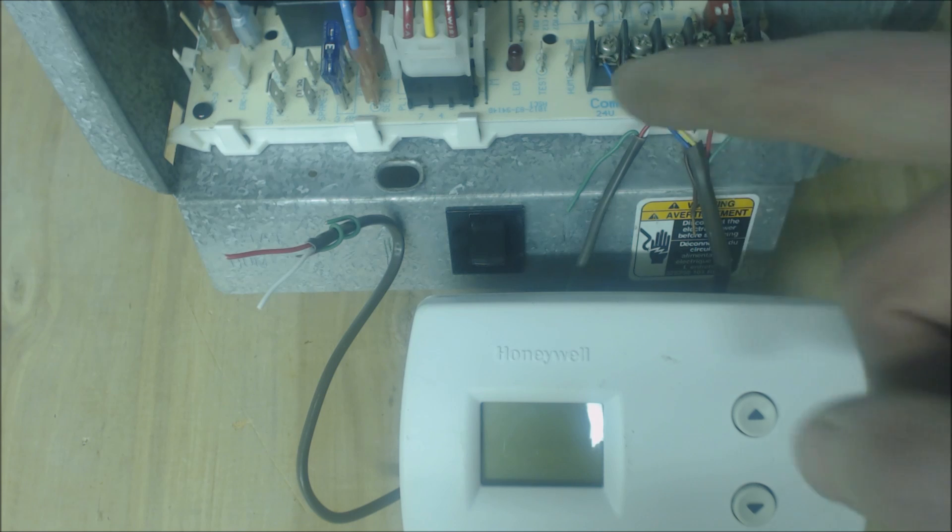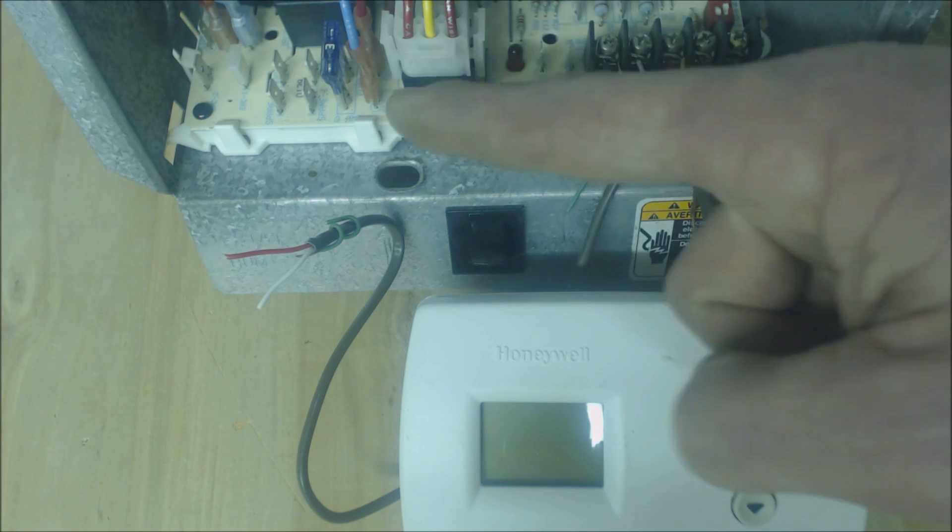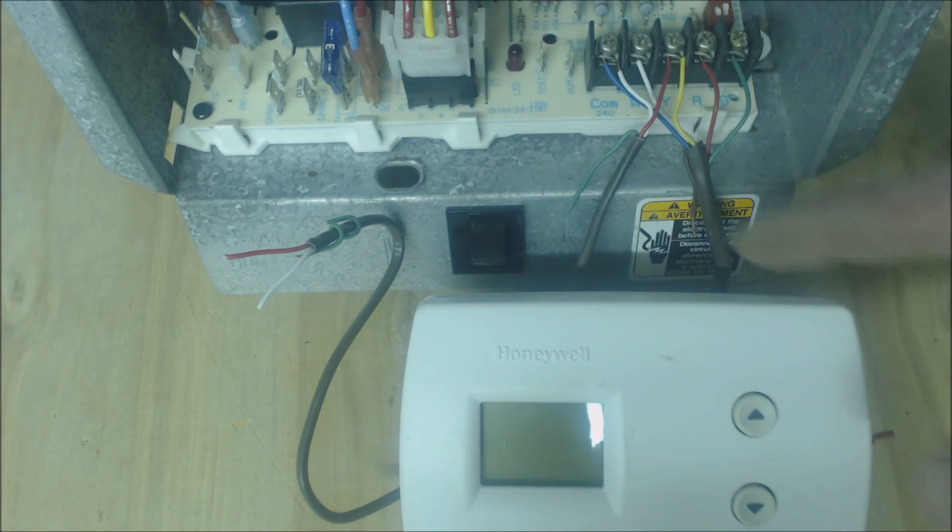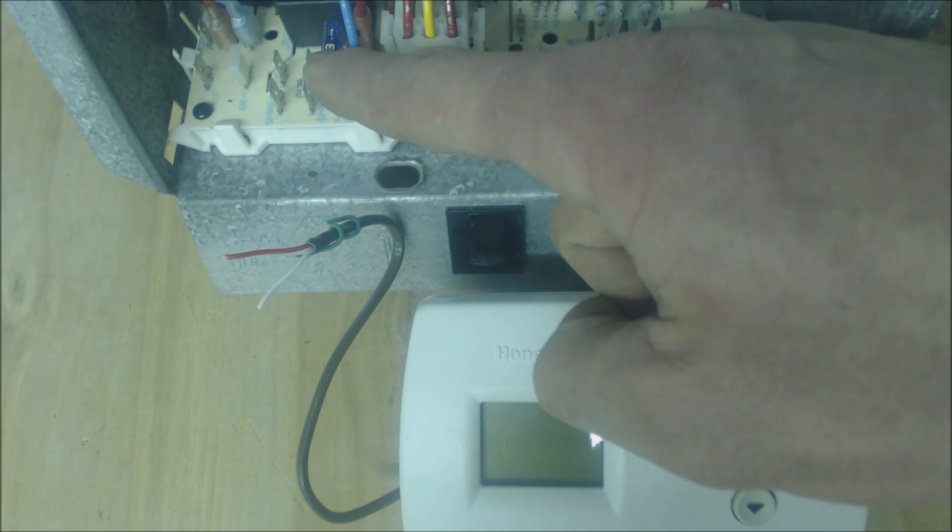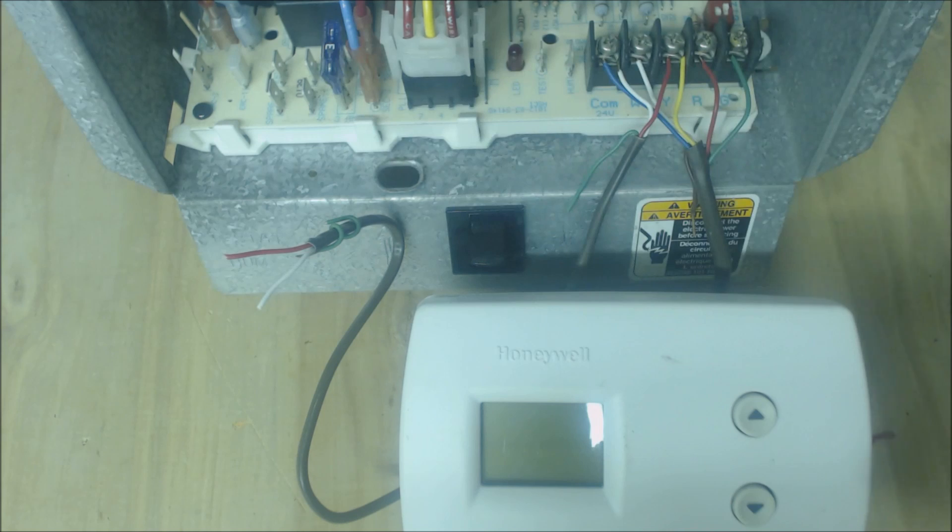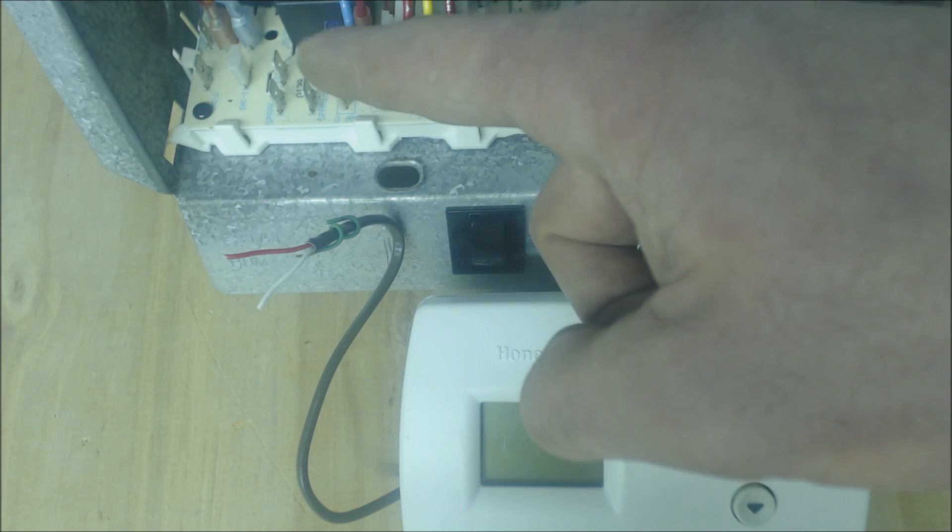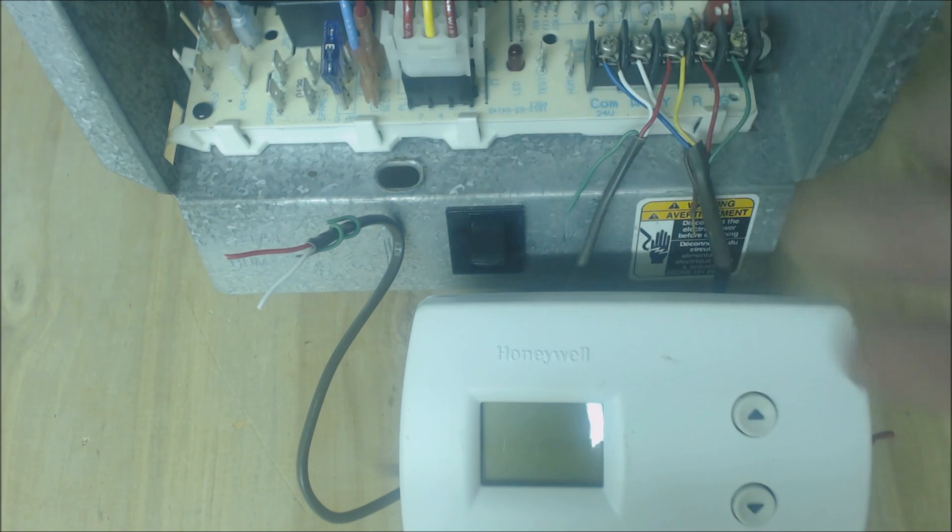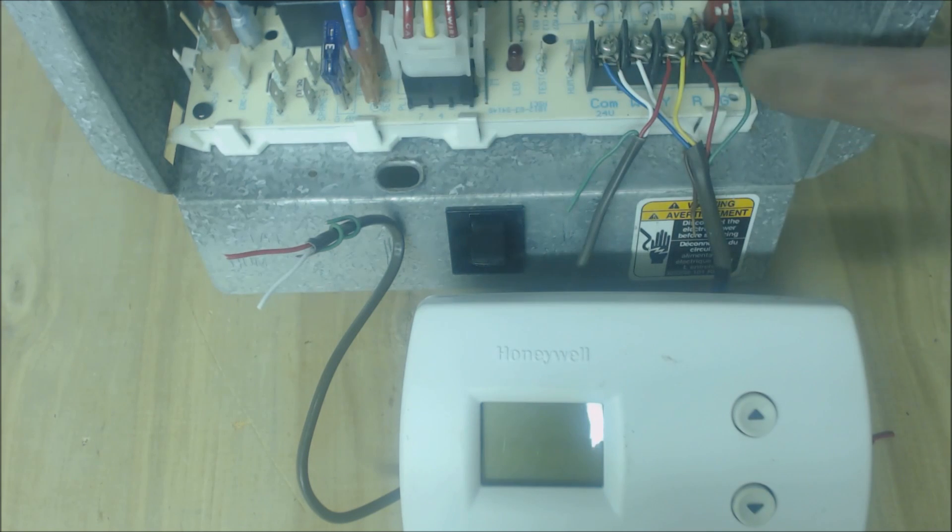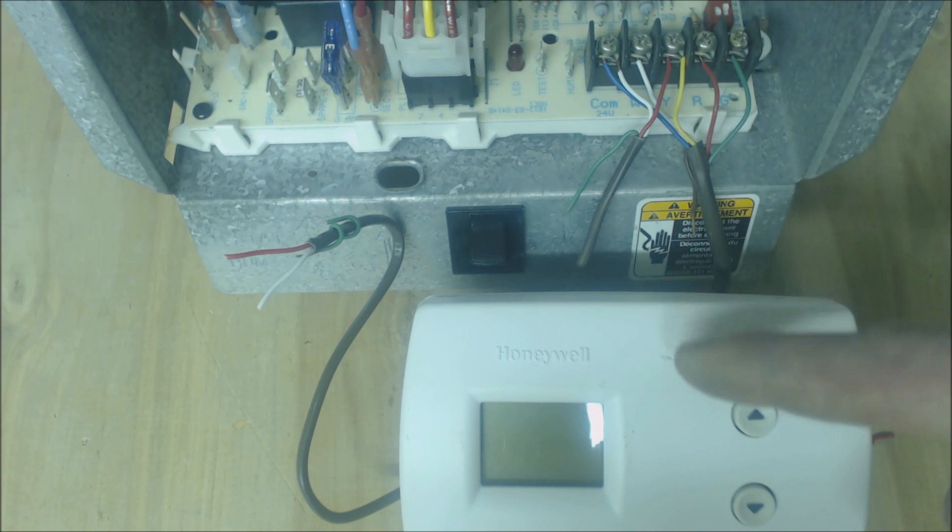In this case we're hooked onto a furnace control board with a 3 amp fuse. What that could mean is that your 3 amp fuse could be blown, not allowing 24 volts to your thermostat.